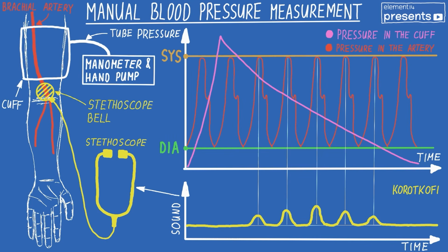Now the yellow peaks here are the Korotkov sounds, and here's when they appear. When we start the measurement, we first pump up the arm cuff to some pressure that's above the systolic. At that point we slowly open the valve and start letting the air out slowly. Once that pressure reaches the systolic value, we can start hearing the pulsations. As it keeps going down, the pulsations will first get louder, then the sound will get lower and lower, until at one point it completely disappears, and that's the point where the Korotkov sounds disappear, and that's the point where the pressure inside the cuff is actually equal to the diastolic pressure, and that's how we measure the systolic and diastolic pressure using this method.